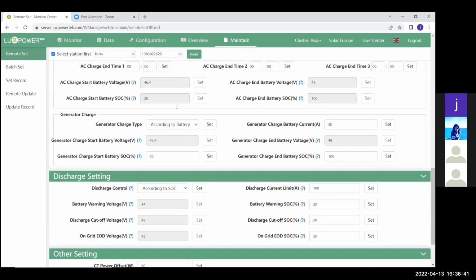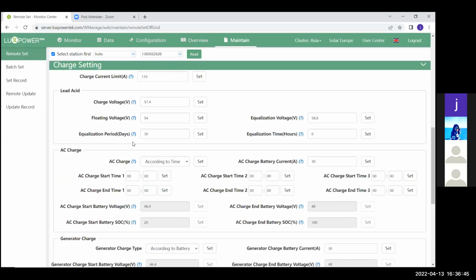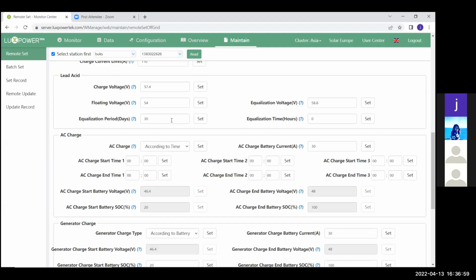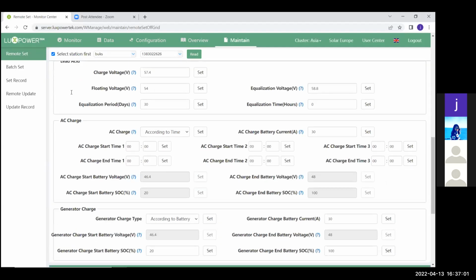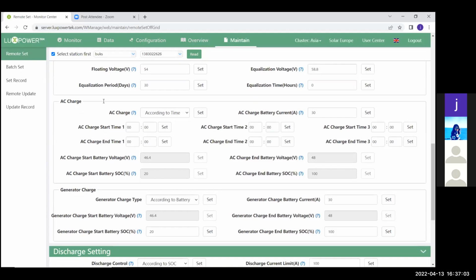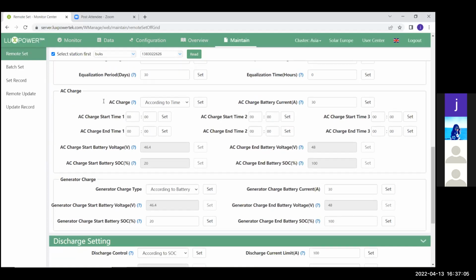You'll put in your charge voltage, your float voltage. This equalization period setting that's here is not applicable at the moment. It's a function that isn't activated on these machines. So you don't have to worry about the specific function. It's not activated on the machine at present. AC charge.